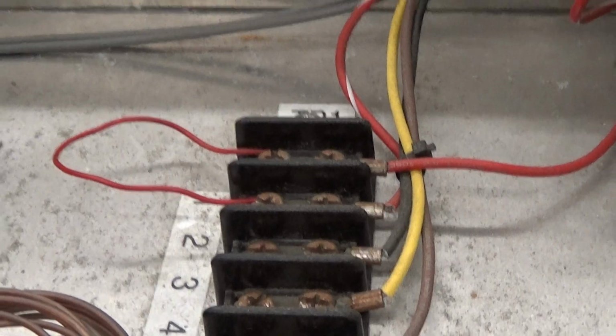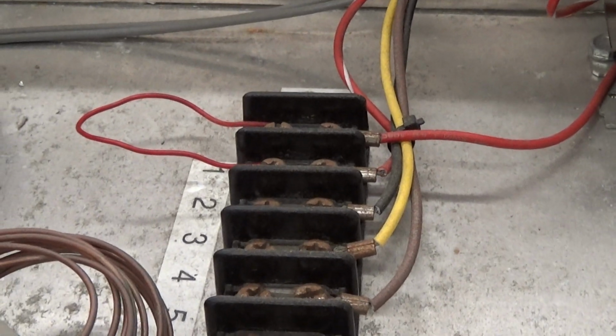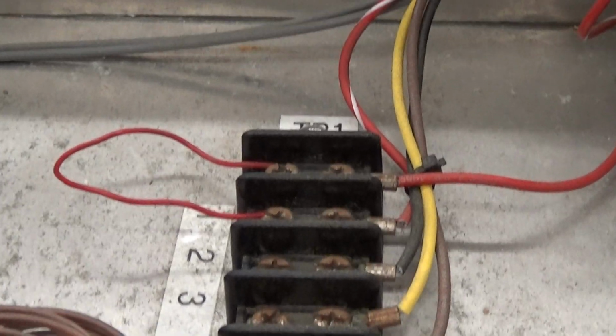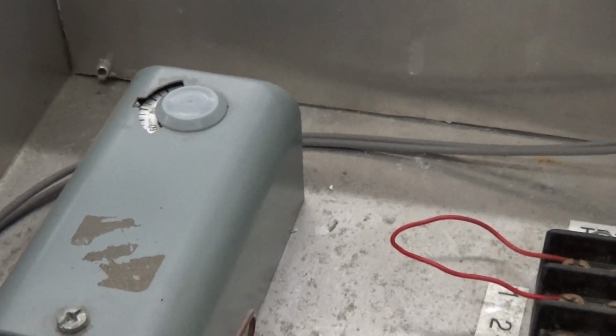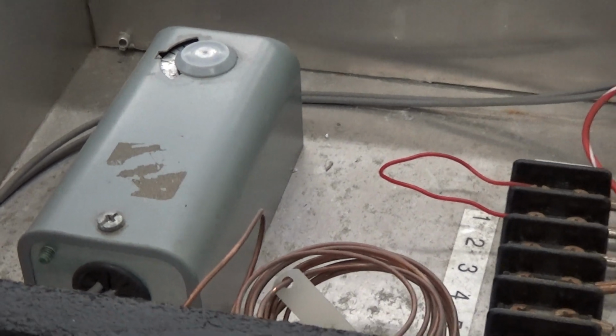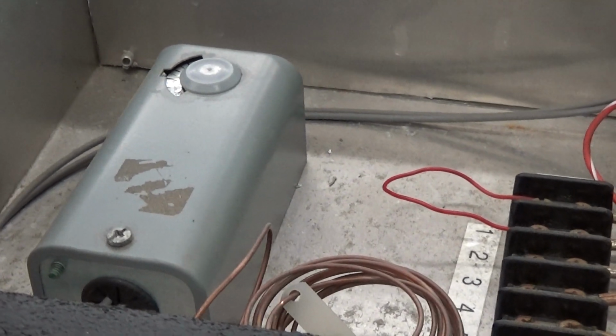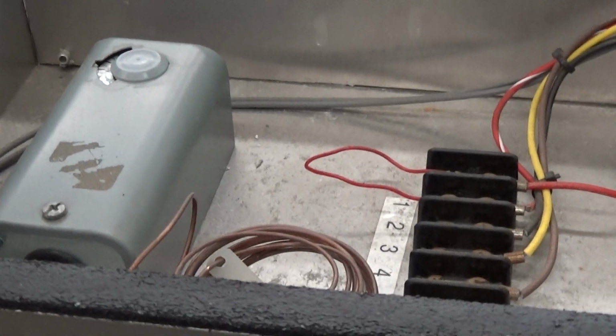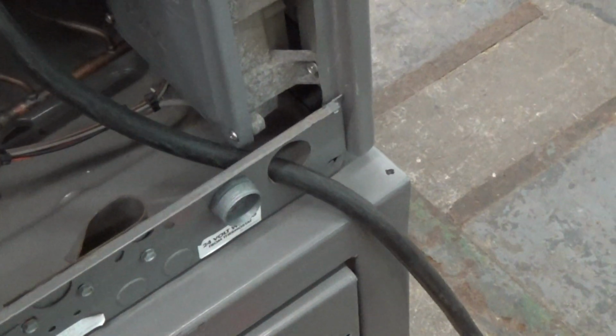While we're up here, notice this terminal strip here. We have that jumper. That should stay in there unless you want to have a remote on-off start. And that's terminals 1 and 2. What we see here, this Johnson Controls controller, that's actually a thermostat for the low ambient. That's not a freeze stat. So that is already preset for outdoor operating conditions. You do not need to adjust that. You're going to bring power into the chiller from that hole there up into the electrical area where we made the contacts there.